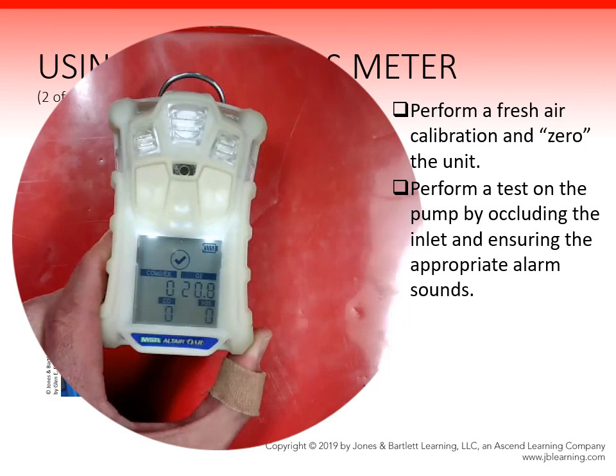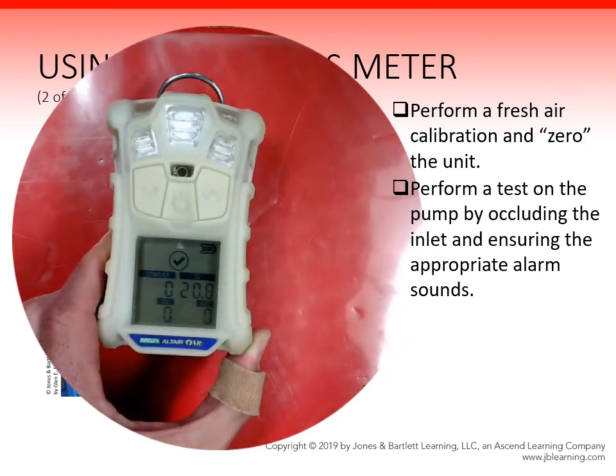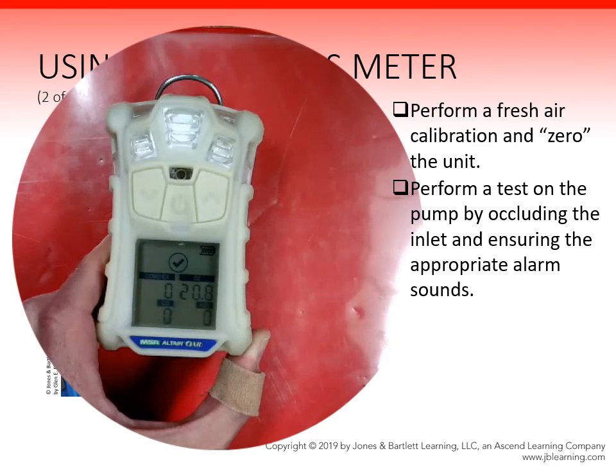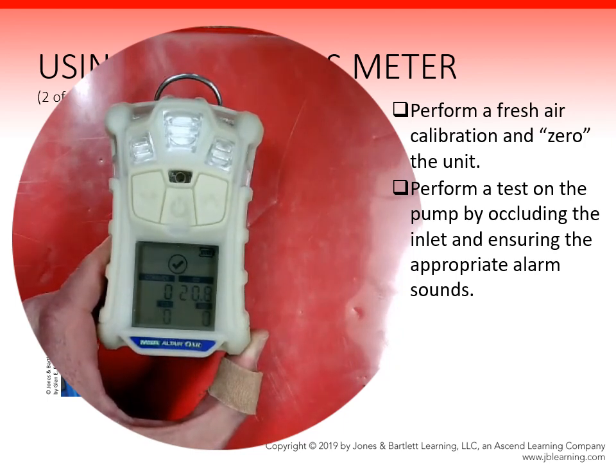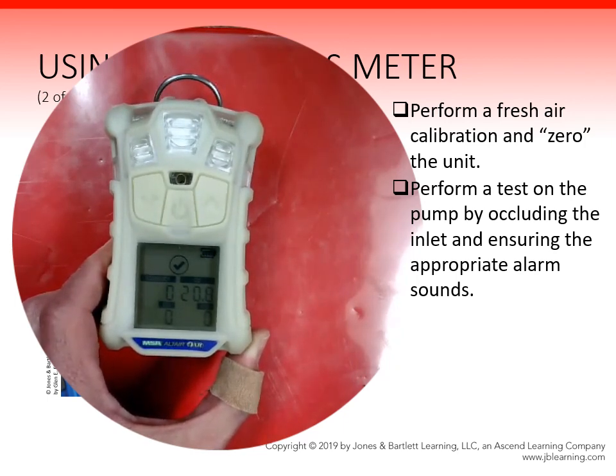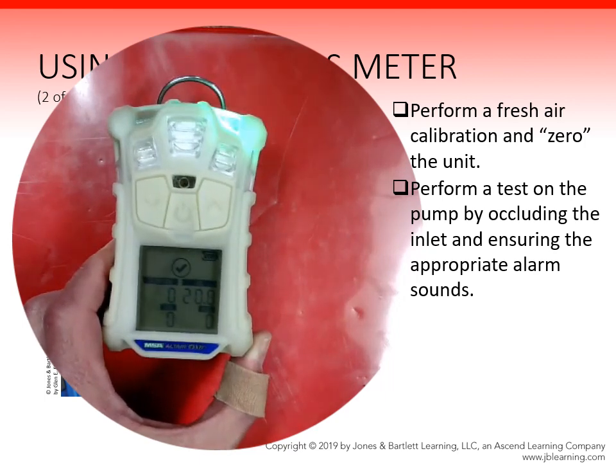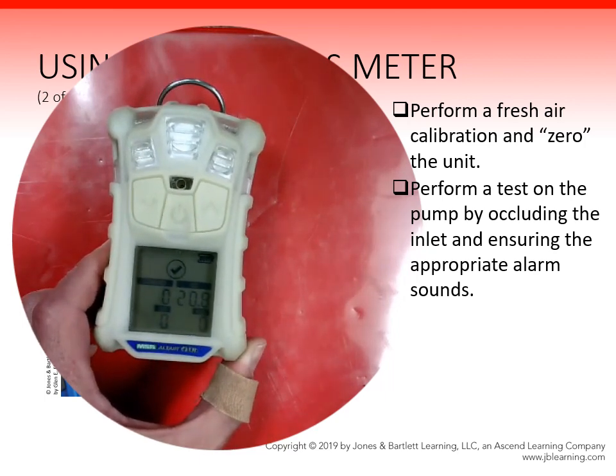It's detected that fresh air is there and at levels it expects, so it gave us a pass notification. Now you can also use the arrow key to bypass that fresh air setup if you're not in a fresh air environment, and it will remember what the last fresh air calibration settings were. So if you happen to have to turn this on in an area that could be contaminated, it won't affect your readings that way.